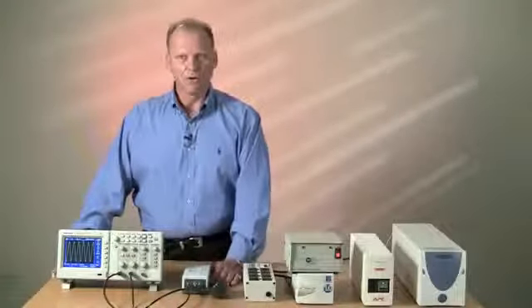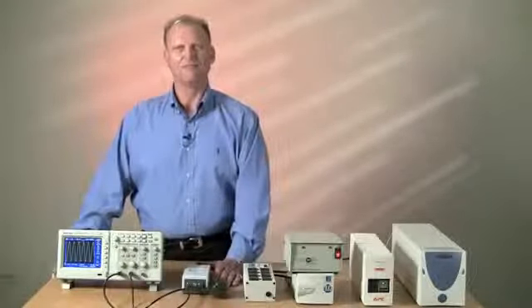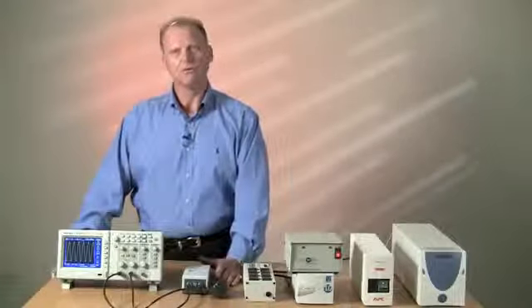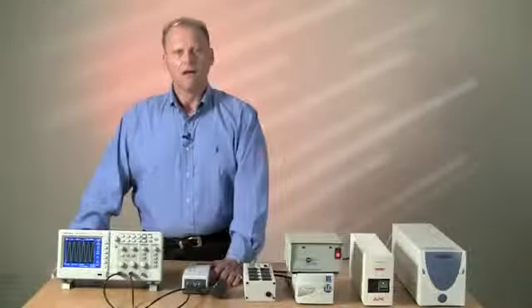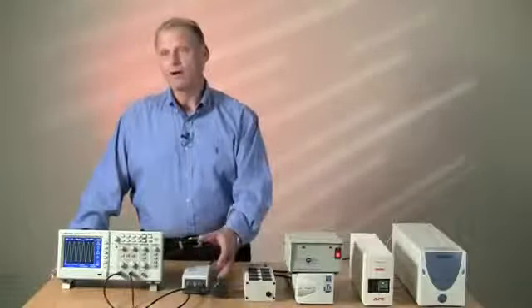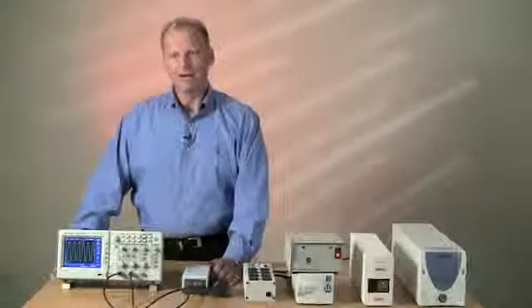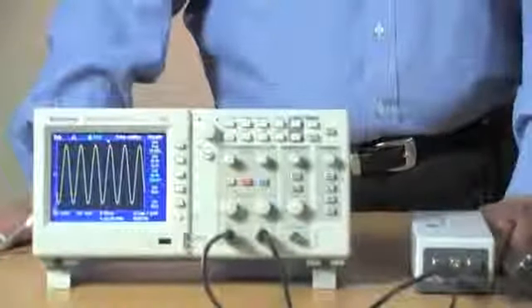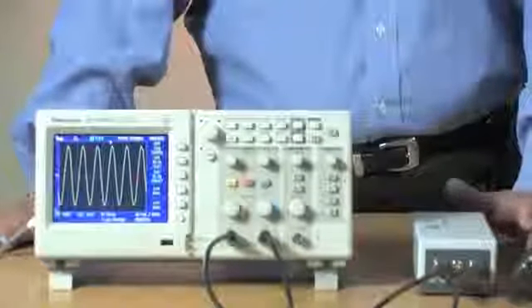The first is the noise between hot to neutral, or phase to phase, which I'll refer to throughout the demo in terms of destructive levels of noise. The second probe lets me look at the noise between neutral and ground.